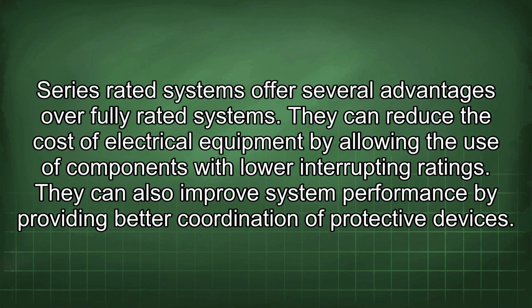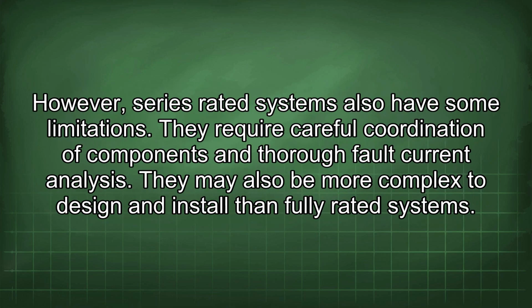Series-rated systems offer several advantages over fully rated systems. They can reduce the cost of electrical equipment by allowing the use of components with lower interrupting ratings. They can also improve system performance by providing better coordination of protective devices. However, series-rated systems also have some limitations. They require careful coordination of components and thorough fault current analysis.